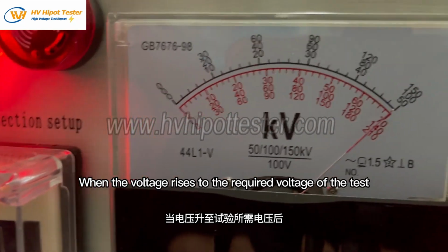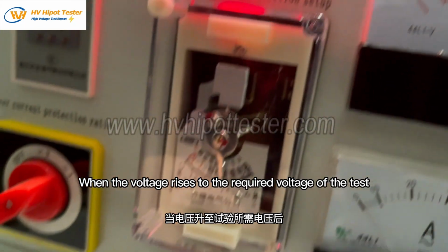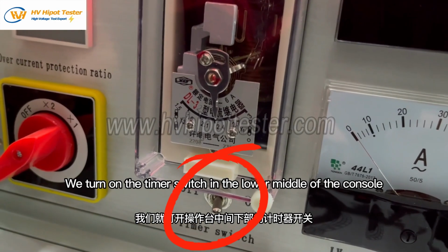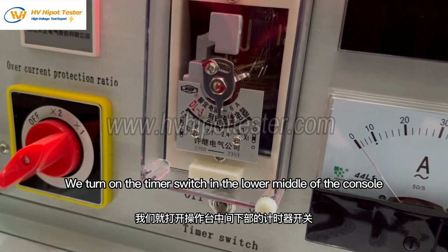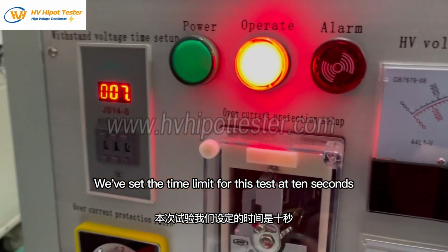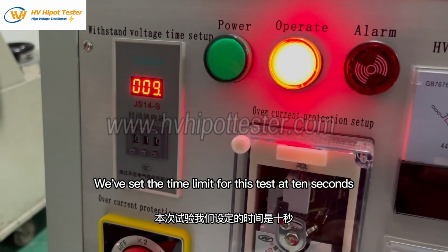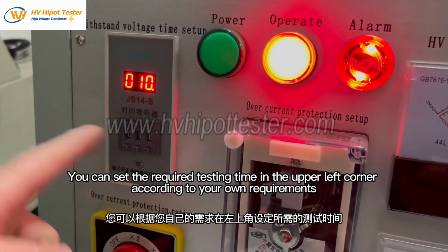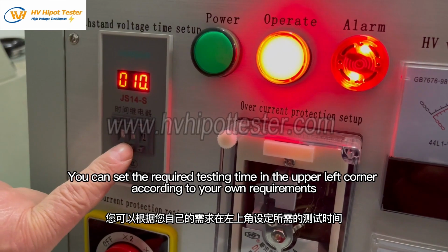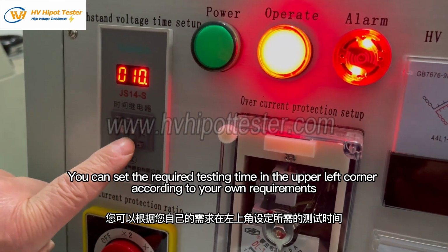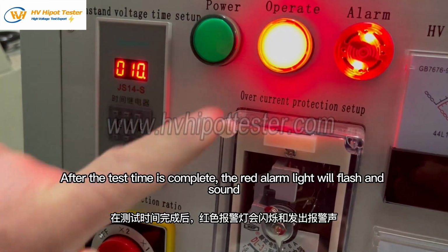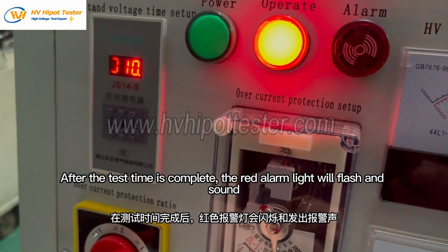When the voltage rises to the required voltage of the test, we turn on the timer switch in the lower middle of the console. We've set the time limit for this test at 10 seconds. You can set the required testing time in the upper left corner according to your own requirements. After the test time is complete, the red alarm light will flash and sound.